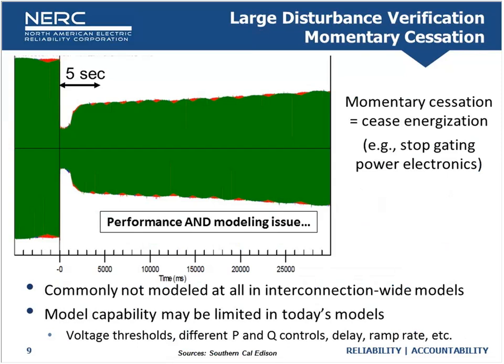What we're seeing is that a lot of times the plant response does not match the model. It doesn't necessarily mean it's a modeling deficiency — it may just be a communication deficiency in understanding how these plants are actually behaving. Momentary cessation is one issue that kind of hit us quite literally. We've had a number of grid disturbances where we're seeing the use of momentary cessation — the ceasing of energization of current into the grid by these types of resources, particularly in the solar world.